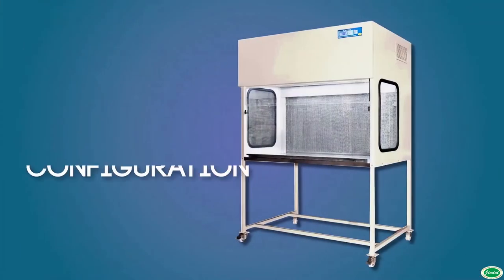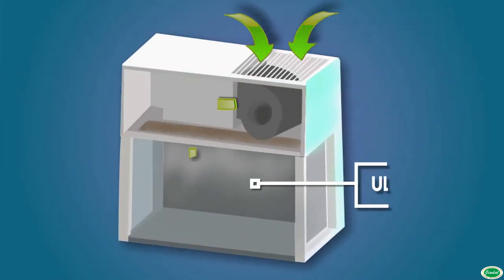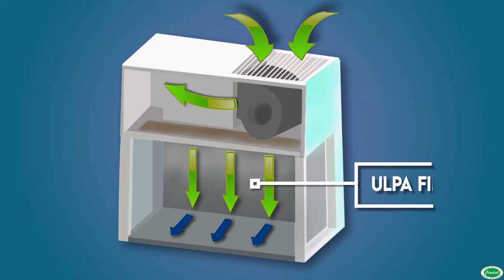All laminar flow clean air cabinets are basically constructed with an outer body of mild steel dually powder coated. The inner work table is made of stainless steel.